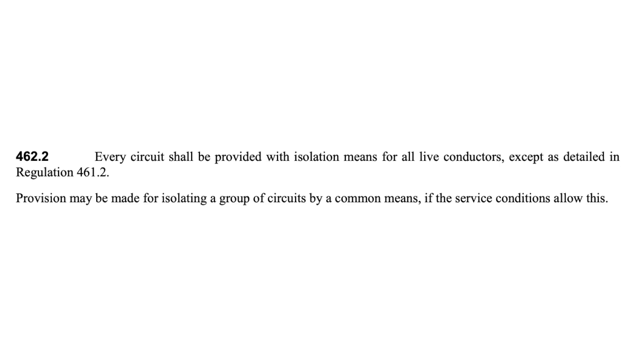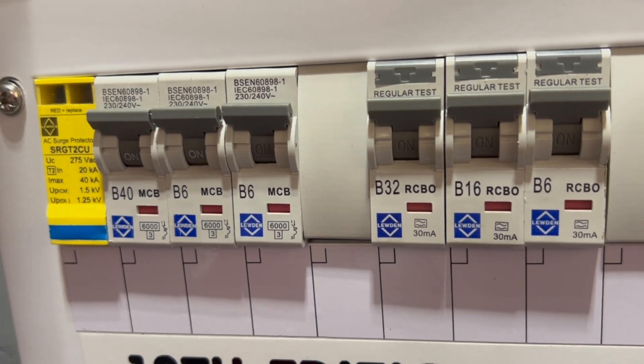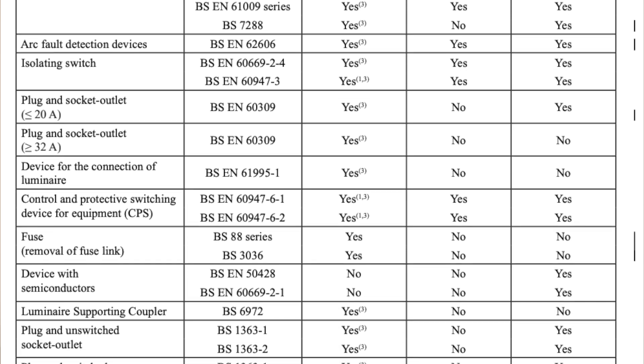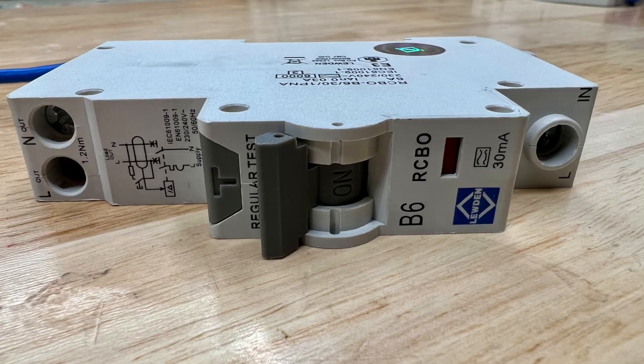However, Regulation 462.2 also says that provision may be made for a group of circuits by common means if the service condition allows this. What this means is we can use the double pole main switch as a means of isolation. However, we need to bear in mind that if any of the protective devices are intended to be used as a means of isolation, then we would need to use a double pole protective device. For example, if we look at table 537.4, which is on page 184 of BS7671, the table lists types of protective and switching devices and shows which devices are suitable for isolation, showing that MCBs and RCBOs are suitable for isolation. However, note 4 refers to Regulation 462.2, which says that every circuit shall be provided with isolation means for all live conductors except as detailed in Regulation 461.2. So to summarise, if you're working on a TT system and the protective devices are intended to be used as a means of isolating circuits individually, then double pole protective devices will be required.